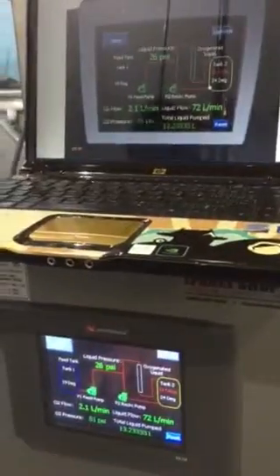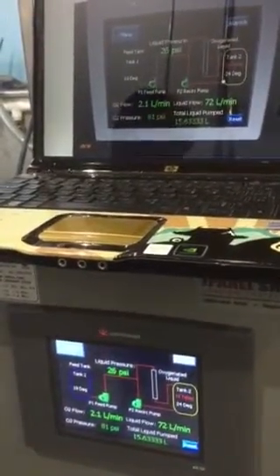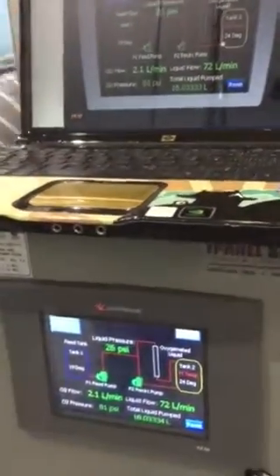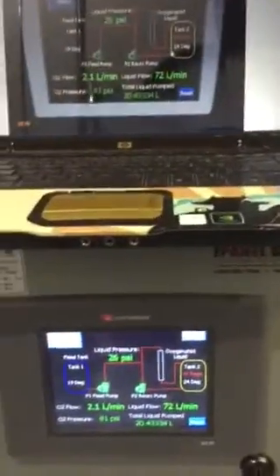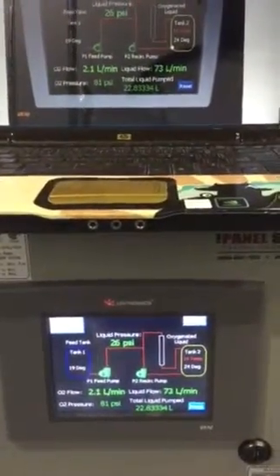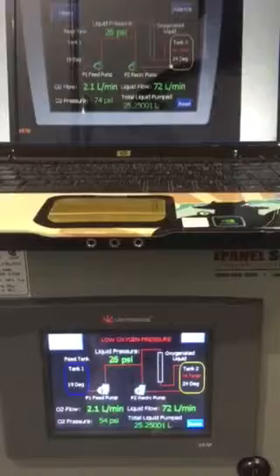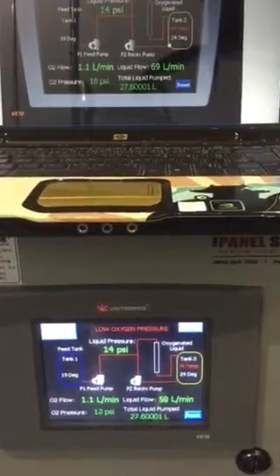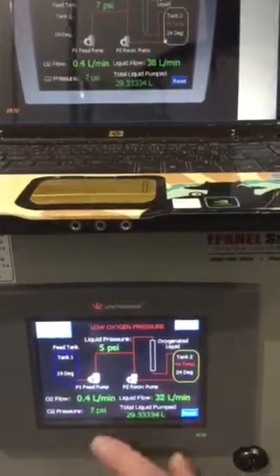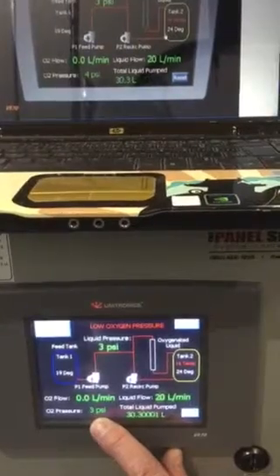For oxygen pressure, what I'm going to do is I'll just pinch off the line. So just keep recording that. I'm going to pinch off the line. So it should drop below 60 pounds. We've lost our oxygen pressure, the system shuts off. You can see down here.